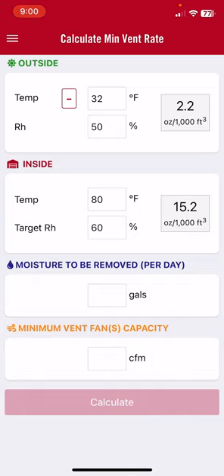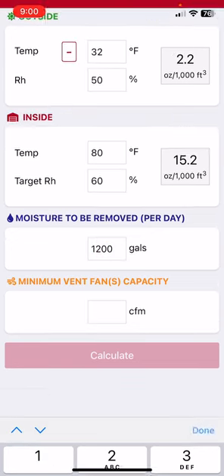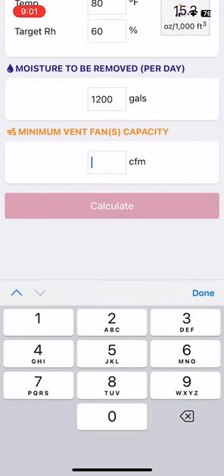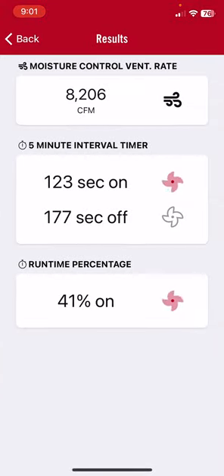We put in the moisture removed — that is how much water the birds have consumed in a given day. Let's say yesterday they drank 1,200 gallons. We then put in our minimum ventilation fan capacity. Let's say we're using 36-inch fans for minimum ventilation and each moves 10,000 CFM, so we enter 20,000 CFM.